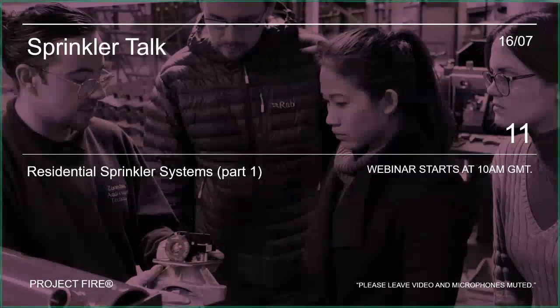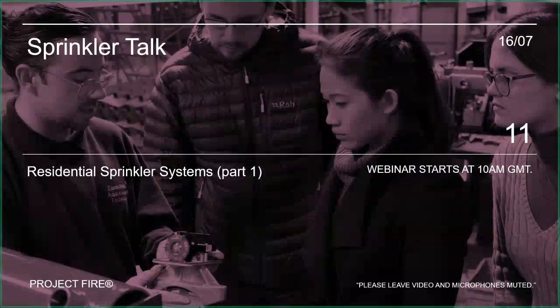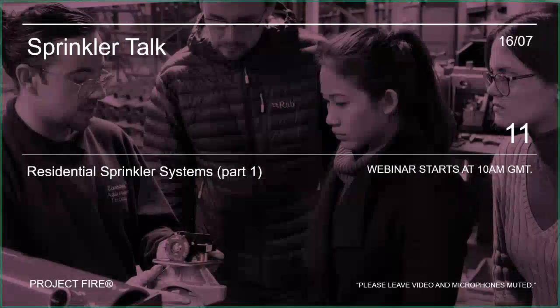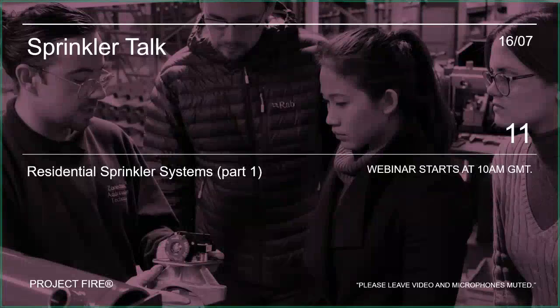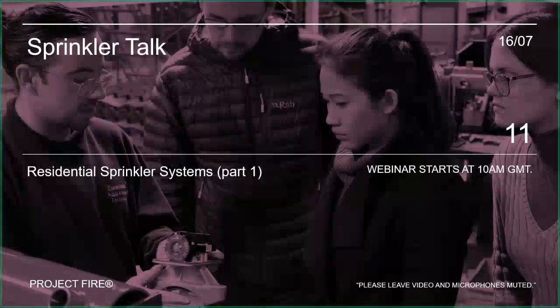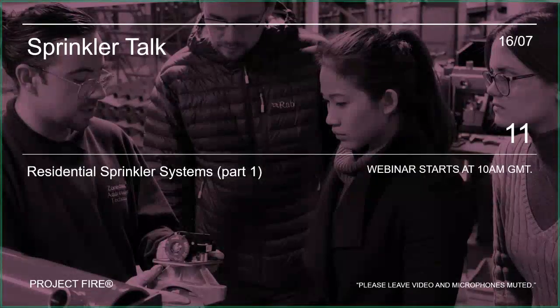Last week we looked at sprinkler heads in a bit more detail — that was sprinkler heads part two. I very bravely gave you a live demonstration of the sprinkler heads activating in hot water, looking at the difference between a quick response head and a standard response head when I dropped them into a hot water bath. You got to see the difference in RTI, the response time index, between the quick response and the standard response head.